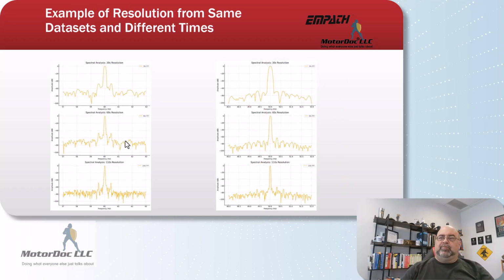Why is resolution important? Because as the bin size is large, so this would be 30-second resolution, same machine, same set of data, real data, by the way. This is less than a horsepower machine. This one is a 100-plus horsepower machine. If I come down here and I take 30 seconds versus 60 seconds, you can see that I've got a lot more information here.